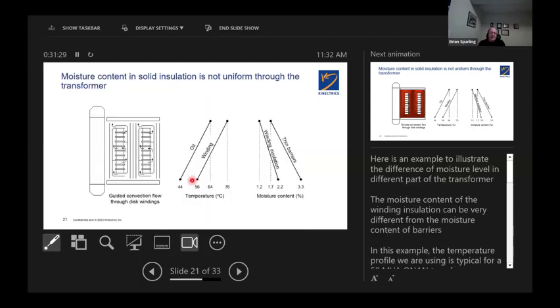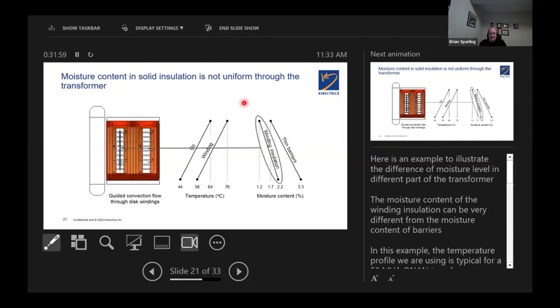So when you cut the transformer, when you slice it in half, as I say, and you look at it, you have convection. This is a cross-sectional view. In the transformer, you have a temperature gradient between bottom and top of the tank, right? The oil is cooler at the bottom than the top. There is a winding temperature indicator gradient, and it's cooler at the bottom than the top. That's just the way it works. It's physics. Moisture content in the winding is a mirror image of the temperature. So it's drier at the top because it keeps pushing the moisture out more than the bottom. It's cooler. So the moisture isn't coming out of the paper as much.